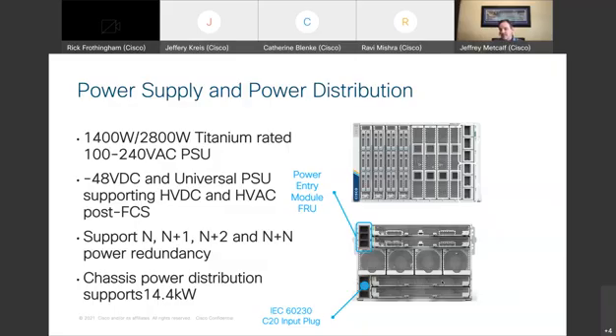What we've done is changed that power entry module to be a FRU. So if a colo facility changes and the power delivery is different, you have the ability to change the FRU module or the power supplies in the field—you don't have to do a complete chassis swap. Or, if there's an acquisition and equipment comes into a company's data center that was provisioned for a different type of input, you can easily swap these out to maintain the ROI.